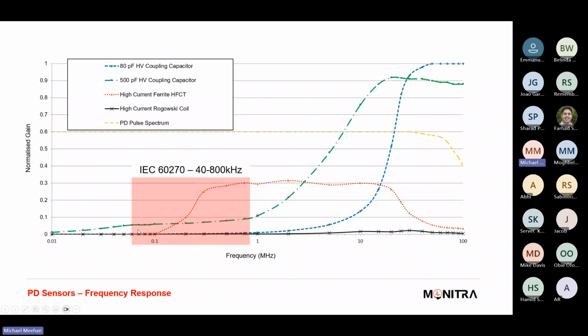And when we see here, you've got the output response from your measurement units, and at 500 picofarads, we have very good high gain. So we can get some good sensitive measurements from PD activity in this whole frequency range. Similar to the high frequency CTs, we have a good frequency response throughout this range. And it's important to have that sensitivity at 500 picofarads. We can see deeper into the winding and get that extra sensitivity.